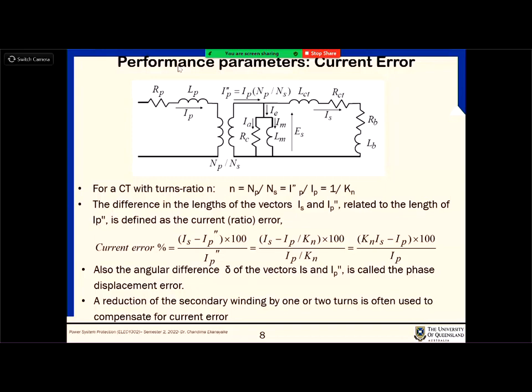If you look at this equivalent circuit, this is the real primary current, and this is the real secondary current. But the turns ratio is giving the relationship between the primary current and IP double dash, not IS. So if someone gives you a CT saying that the turns ratio is 100 to 1, and there is a 100 amp current going through the primary, we assume that it has to be 1 amp. But with that turns ratio, that 1 amp is actually IP double dash. IS, or what you measure in the secondary, could be 0.9 amps because of this excitation branch, right?